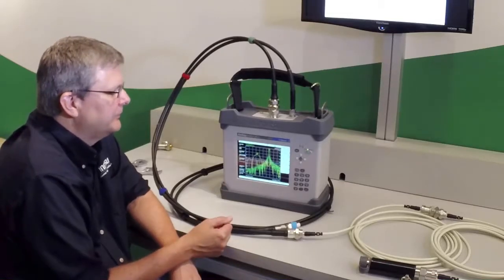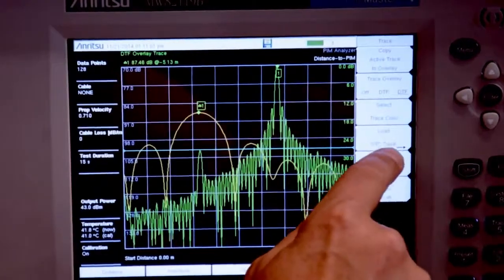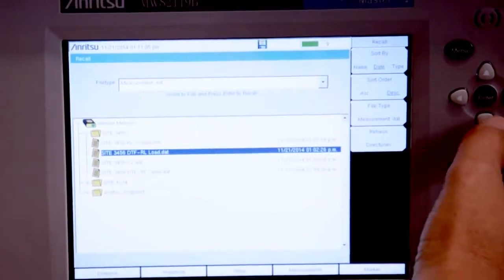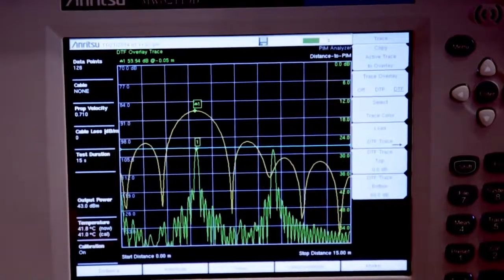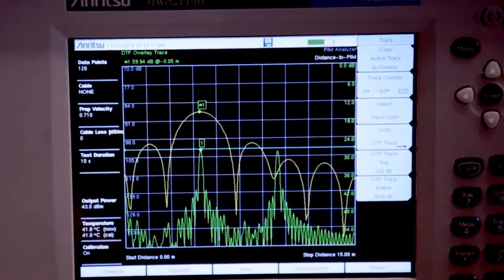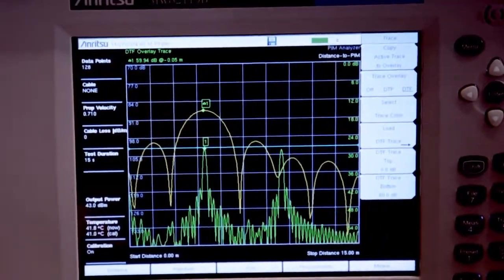In a closed antenna system, or a system where we think the PIM source is internal to the system, a more useful trace to load is the distance to fault trace where we had the precision load at the end of the cable. So here we use, once again, the high resolution of the cable and antenna analyzer mode and see a very clear picture showing us exactly where each connector is.